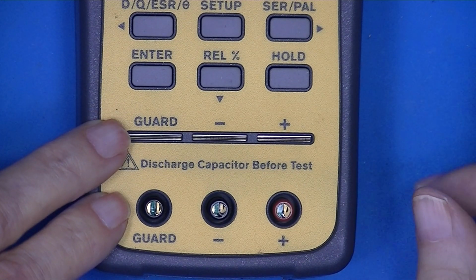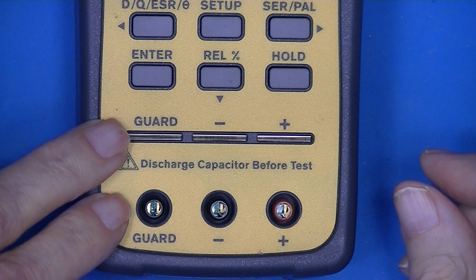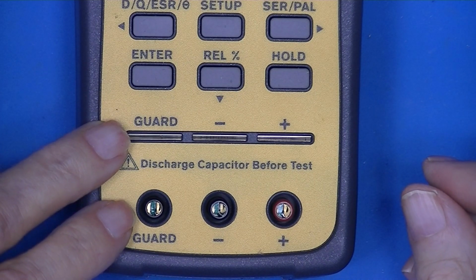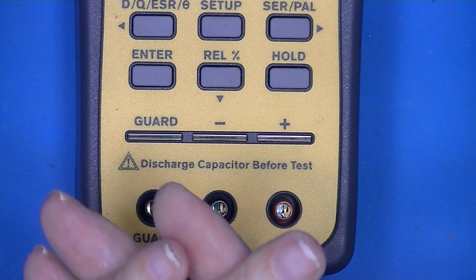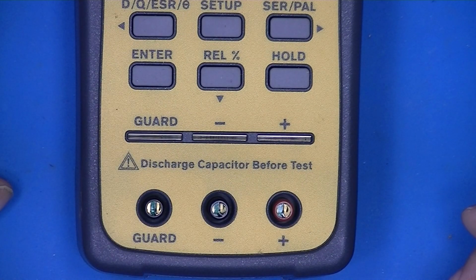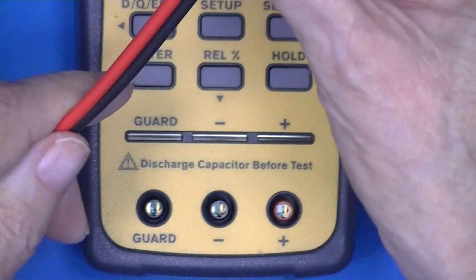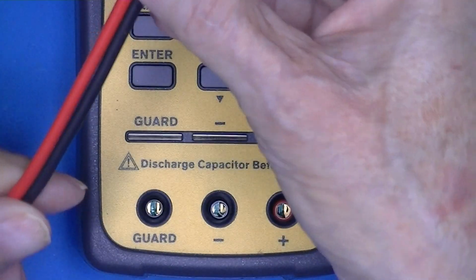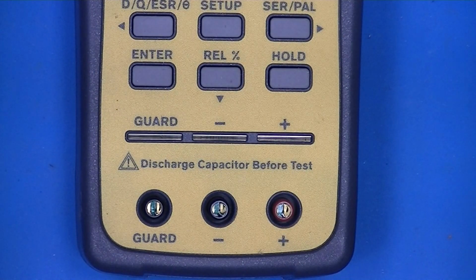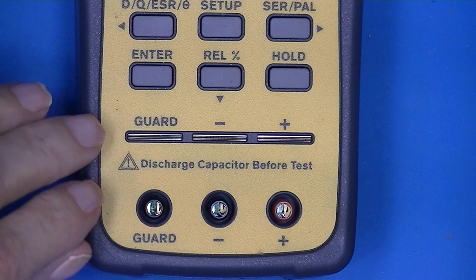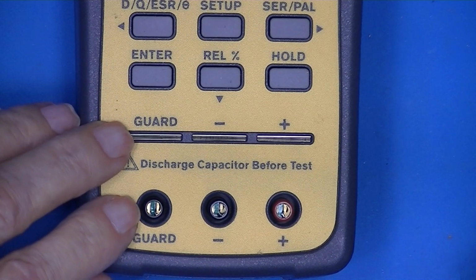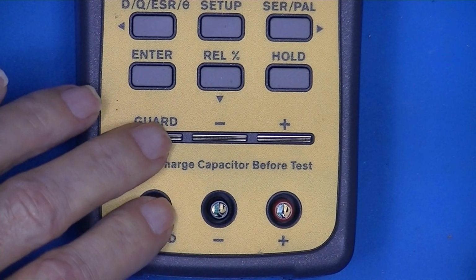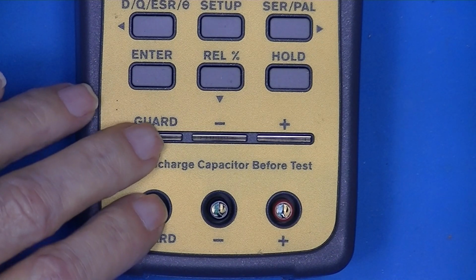Because we're using RF or AC, the positioning of the leads relative to each other becomes important. So to minimize that effect of having some capacitive coupling between the lead and some inductance based on the length of the lead, we will guard the leads. Guarding means shielding.